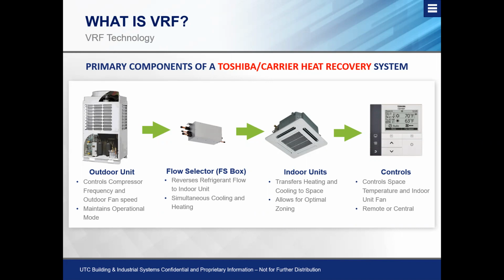Okay, but as a rule of thumb, when we're comparing associated carrier to carrier, we now know that the carrier system separates the 3 states of refrigerant in a multi-port distribution controller on the heat recovery system. And the Toshiba carrier heat recovery system separates those 3 states of refrigerant in the outdoor unit.